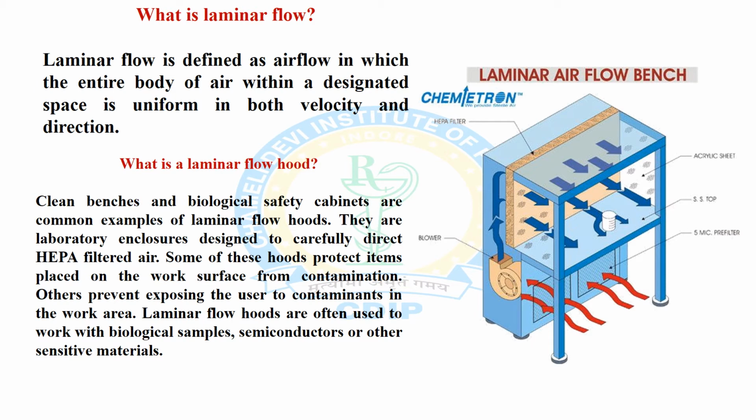So what is laminar flow? Laminar flow is defined as an airflow in which the entire body of air within a designated space is uniform in both velocity and direction. Here is a laminar flow hood. Clean benches and biological safety cabinets are common examples of laminar flow hoods.